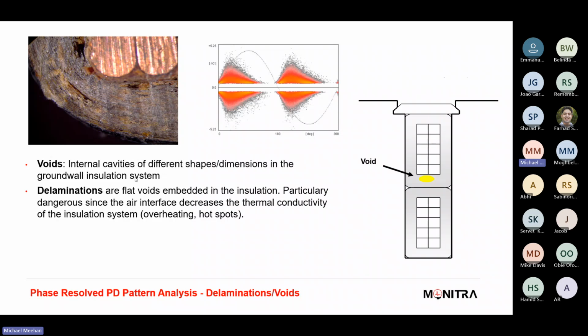The reason we use the phase resolved pattern, which is the PRPD system, is because we know that the PD does correlate with that. So whenever you see any PD reports, you will typically see this. You've got the AC, which is what we call our phase resolved, and you've got your positive and negative cycle. And PD activity will typically form patterns around that cycle, and from those patterns we can start to interpret potential failure modes.